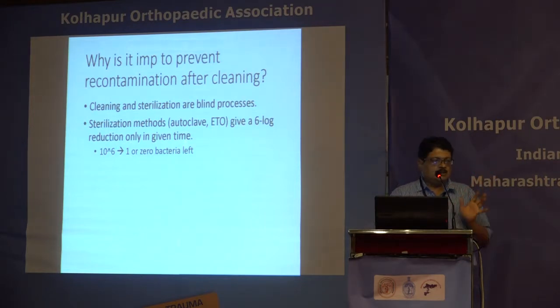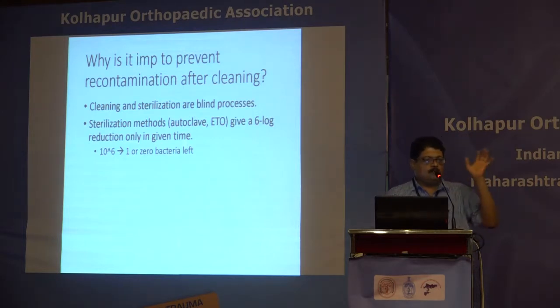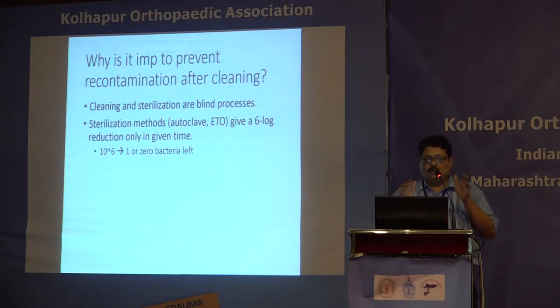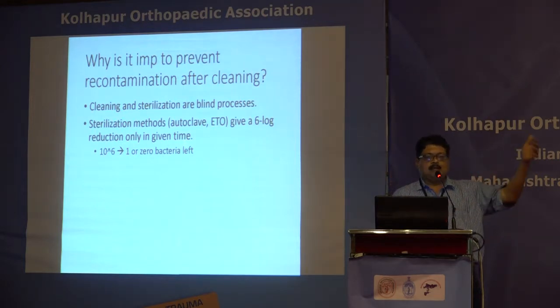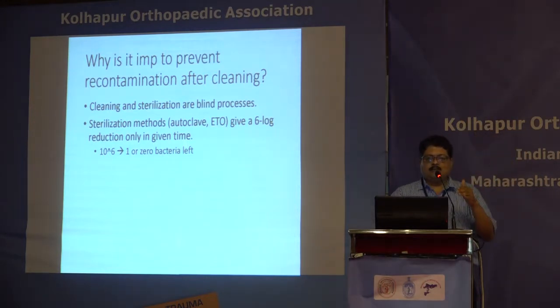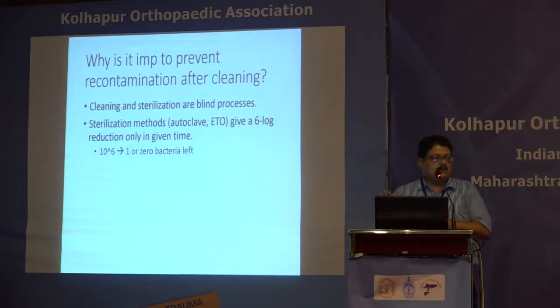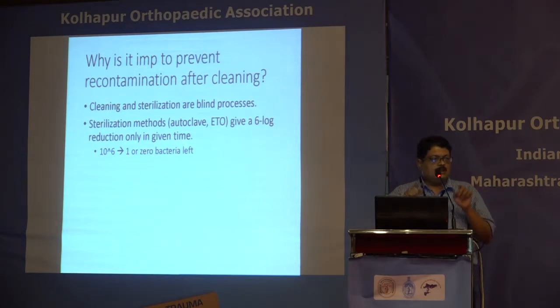For a method to be classified as a sterilization method it must satisfy two criteria: first, it should kill a large number of bacterial spores; second, it should give a 6-log reduction in the bacterial count. So if you start out with 10^6 bacteria on the instrument, at the end of the process there should be one or zero bacteria left — in other words, a one in a million chance that a single viable organism remains. If the process satisfies both criteria, it is called a sterilization method.